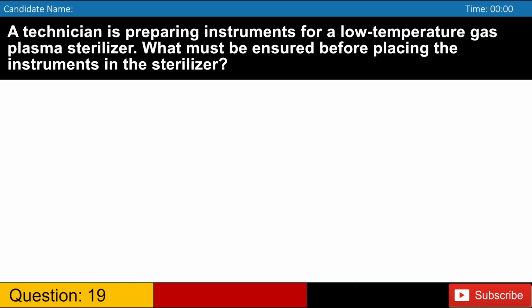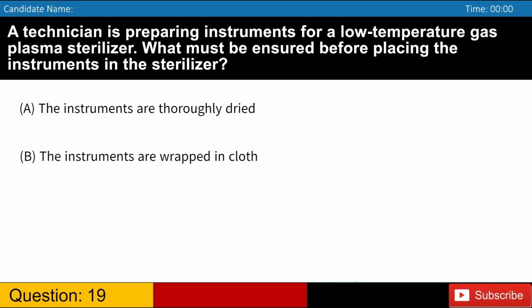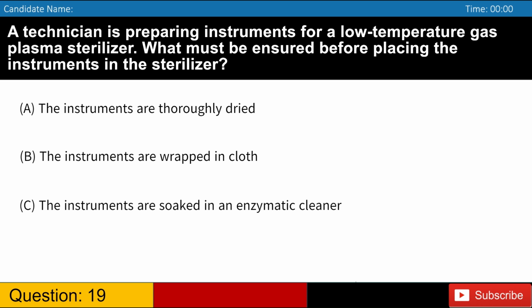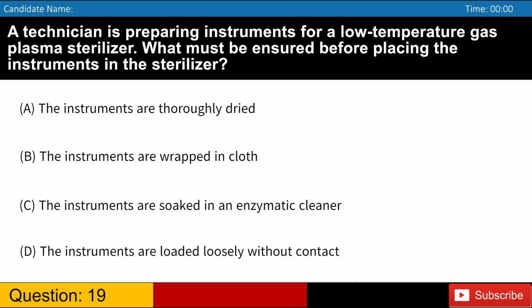A technician is preparing instruments for a low-temperature gas plasma sterilizer. What must be ensured before placing the instruments in the sterilizer? A, the instruments are thoroughly dried. B, the instruments are wrapped in cloth. C, the instruments are soaked in an enzymatic cleaner. D, the instruments are loaded loosely without contact.